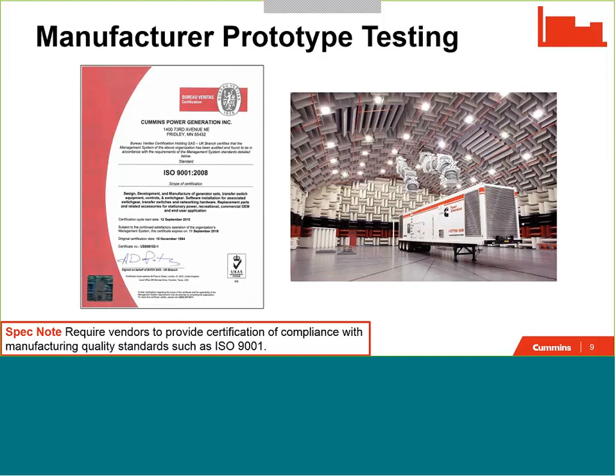That's kind of a process standpoint, but what you don't see in a certificate like this is the actual testing facilities, the actual capabilities that a manufacturer may have. And the capability of a manufacturer highly impacts the quality and the accuracy of the data that's provided with this prototype testing. And so on the right side, what you're seeing is an example of a state-of-the-art facility capable of delivering the highest quality sound testing data in this case. And I'll talk about that here more in just a little bit.